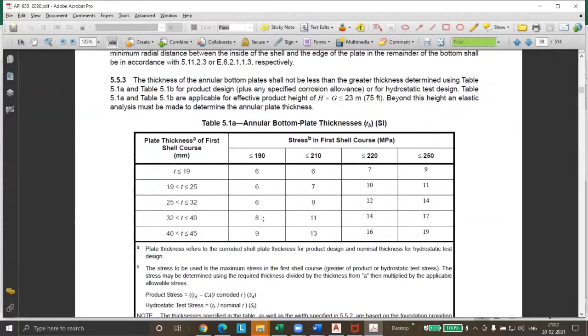So the thickness depends upon the stress. Now the stress is defined as B. The plate thickness is defined as A. What is this plate thickness? Plate thickness refers to the corroded shell thickness for product design, and nominal thickness for hydrostatic test design. So in our case, my plate thickness is 26, so 23 mm. Plate thickness refers to the corroded shell plate thickness for product design, so I need to subtract the corrosion allowance. In our case it will become 23 mm, so for 23 mm it will come into this.